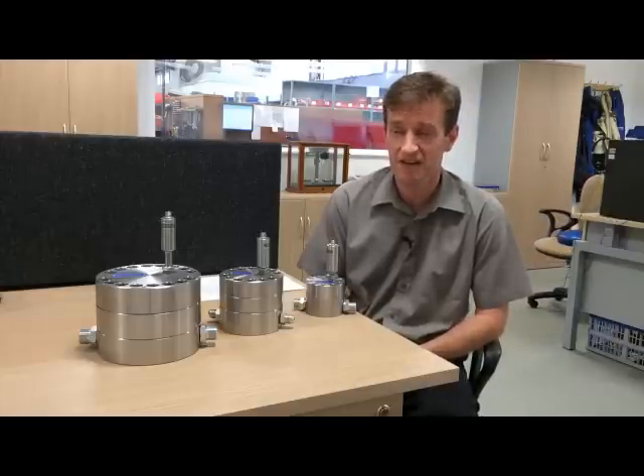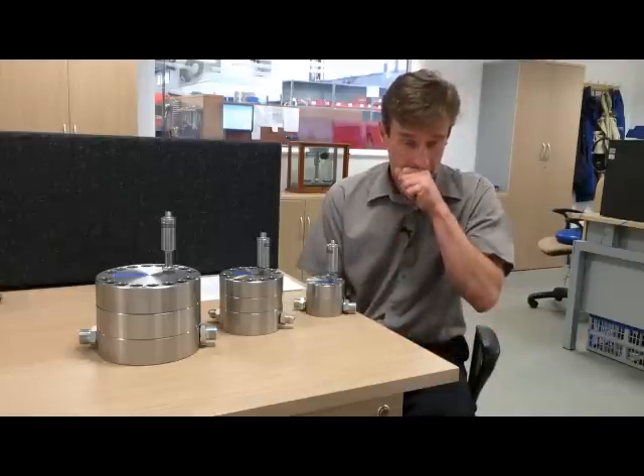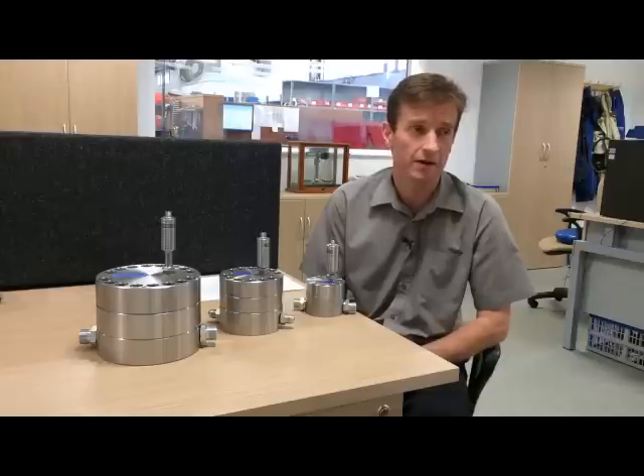Milliamp is far more resilient in industrial environments. Frequency is fairly resistant in industrial environments, especially this type of frequency. It'll be a TTL compatible output and it can be a higher pulse as well. It's an open collector output, so depending where you put your pull-up resistor to, you can have TTL or you can have a pulse output up to the supply voltage if you like.